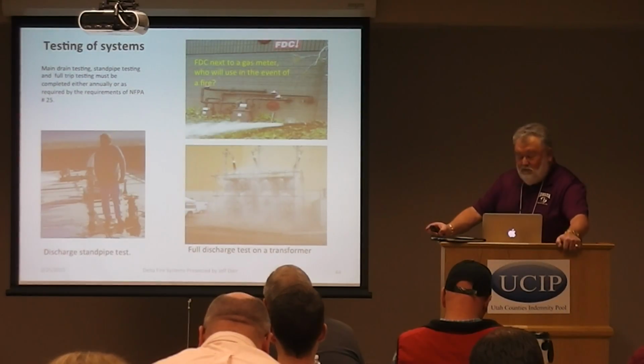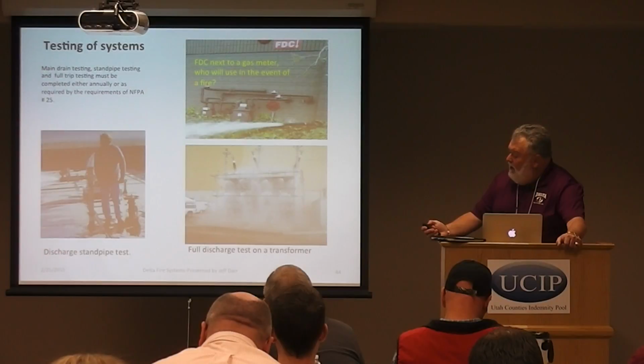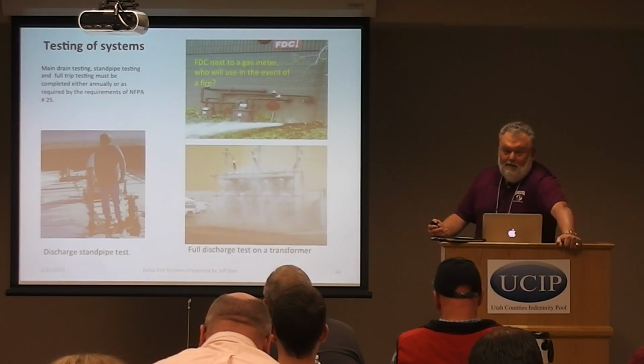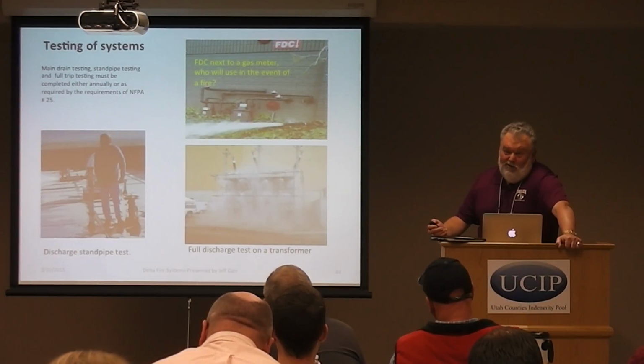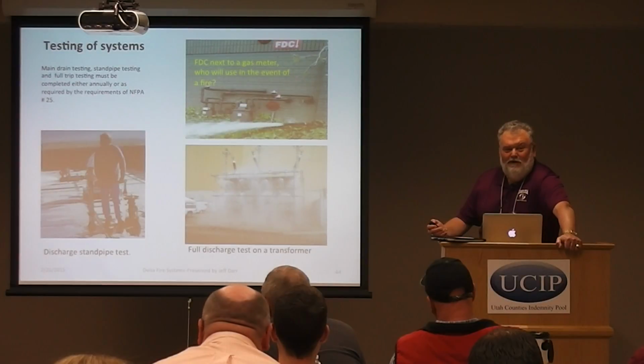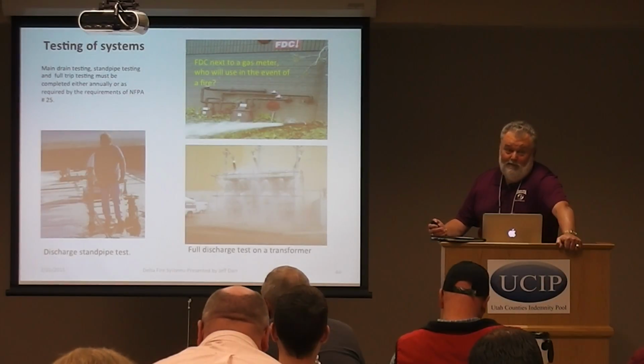And here are the ways we test the systems. Right here, this gentleman's doing a standpipe test on top of a building. And yes, we do flow on top of a building. You'd be surprised at the number of drain systems we find on high-rise buildings that are plugged when you start putting water there, or they're separated. It's a good indication, but it's a bad way to find out that your drainage system isn't working when we're flowing 500 to 1,000 gallons a minute on top of a roof.